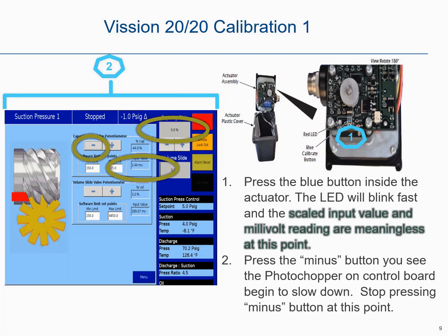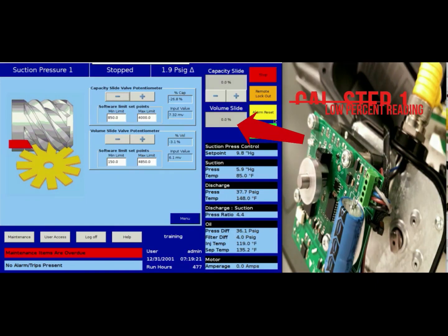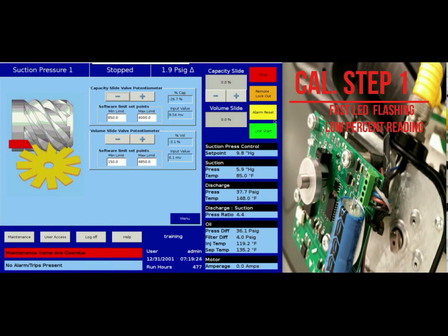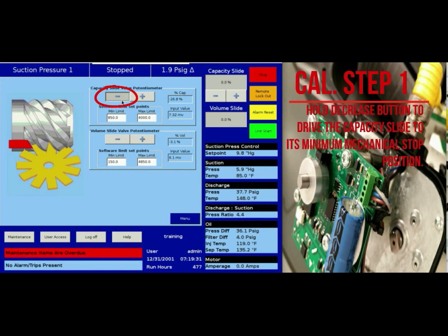After pressing the blue button, the LED light will begin to blink fast, and at this time the scaled input value and millivolt readings will display their minimum value. At this point, you can disregard the display. You are now ready to set your 0% or minimum value. Press and hold the minus button until you see the actuator reach its mechanical stop. You will know when the actuator has reached its mechanical stop when the photo chopper begins to slow down. Also, you will see the command shaft stop to spin.